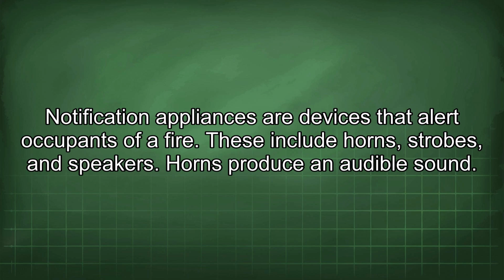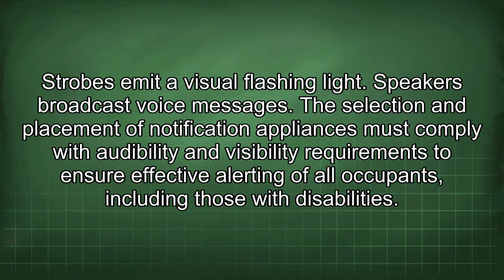Notification appliances are devices that alert occupants of a fire. These include horns, strobes, and speakers. Horns produce an audible sound. Strobes emit a visual flashing light. Speakers broadcast voice messages. The selection and placement of notification appliances must comply with audibility and visibility requirements to ensure effective alerting of all occupants, including those with disabilities.